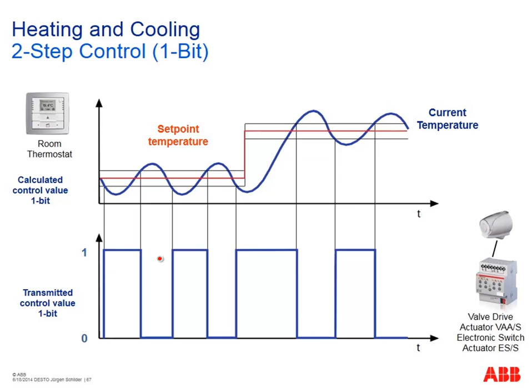This is a digital, let me say, on-off situation, but the electrothermal valve drive itself is not reacting this fast. It takes 2-3 minutes to open completely, so if you start to open, it will slowly open, like this, for example. You see my pointer now, not completely open maybe during that time, and then you give an off telegram or a close telegram, and it will close again. Maybe not completely during this time, but then the next opening command will be set. So it's not a real positioning of the valve drive, but for temperature control, which is very slow, it's very often a sufficient solution. So two-step control, one option.